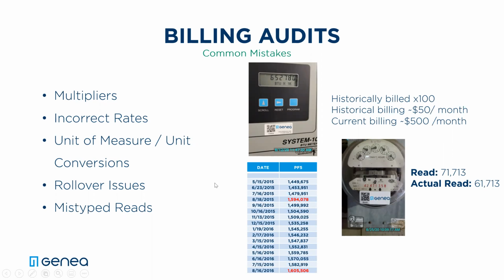Also capturing a rollover: every meter has a finite amount of values it can display, so when it reaches that max value, it rolls over and starts from 0. If your spreadsheet just adds the current read or subtracts the last read without accounting for that, you'll get a negative value or a lower value than should be billed. So there are errors that can happen when using a spreadsheet to calculate things that are constantly moving, without accounting for that, which could cause misbilling.